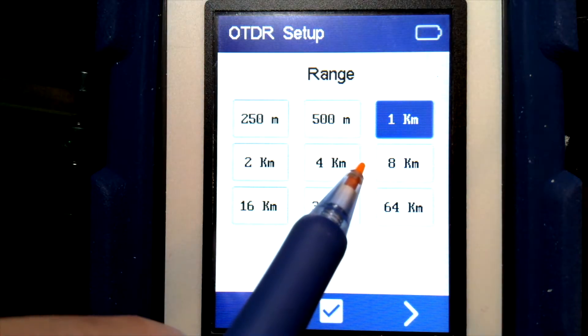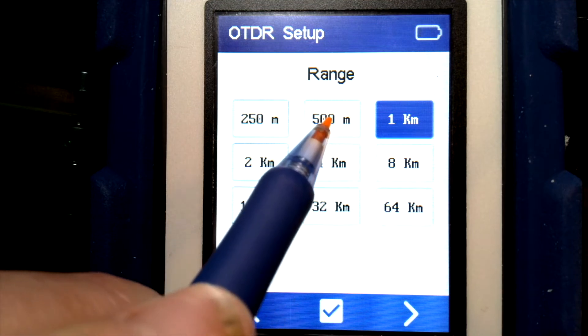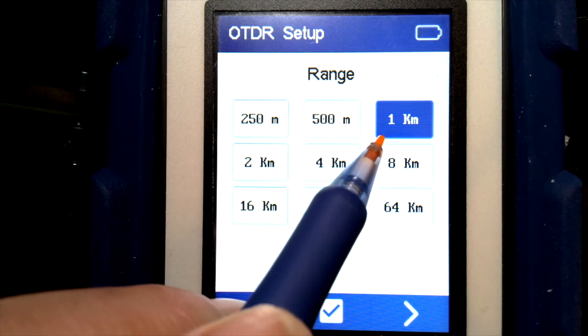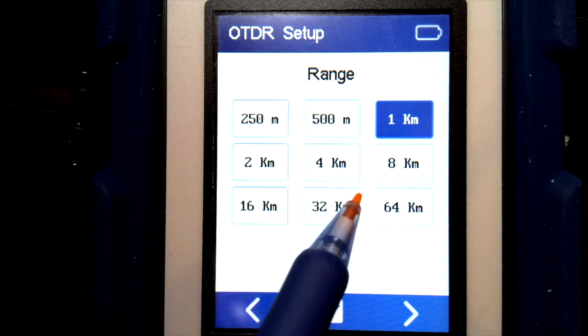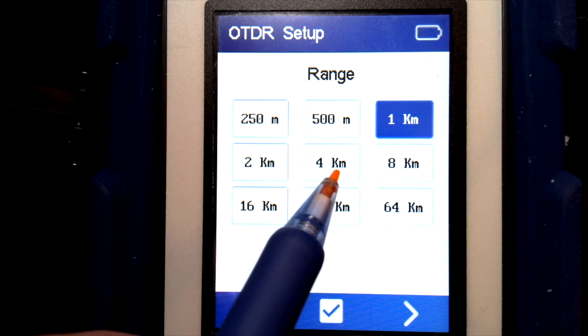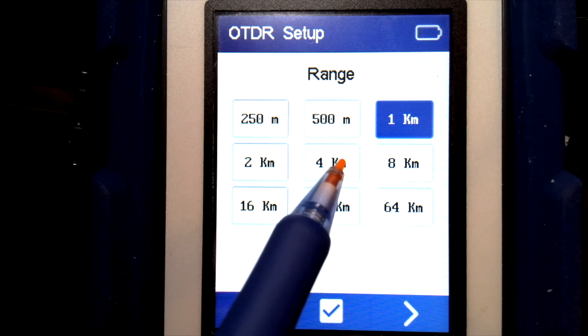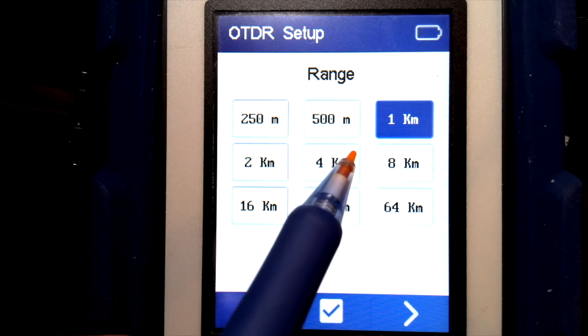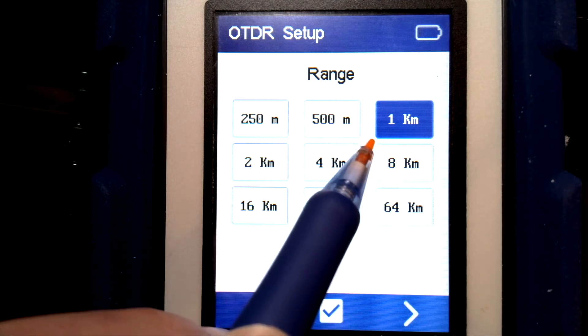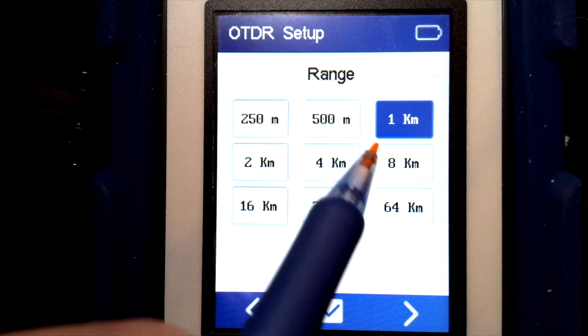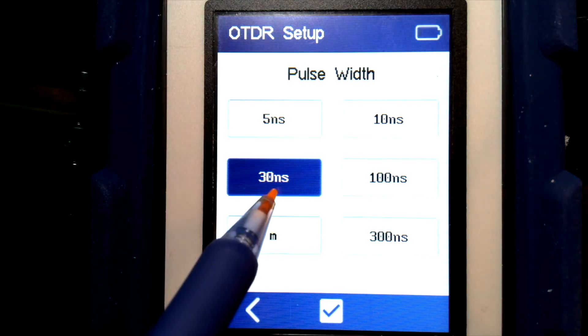The range of the cable should be set to about twice the actual fiber range. The fiber we're testing here is a little over 500 meters, so we'll set the range scale to one kilometer — that's a good rule of thumb. For pulse width, we'll go with 30 nanoseconds.